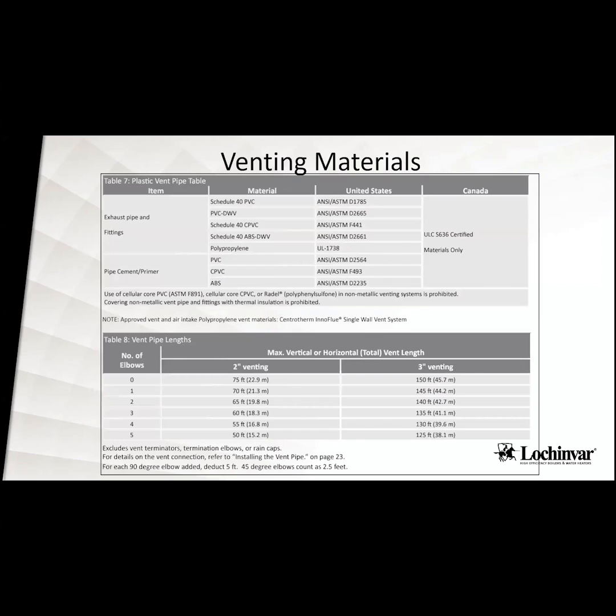So install, this is going to install just like other tanklesses out there in the industry. So you can use 2-inch PVC, CPVC, polypropylene. On here too, it does show that you can use ABS as a vent material for these units. I personally do not like ABS as a vent material, but if you have contractors that are wanting to use ABS as a vent material, it is approved for that. The caveat between that is all of those need to be solid core piping. So with PVC DWV, it just has to have the D2665 stamp on it, but be solid core and not foam core on that.